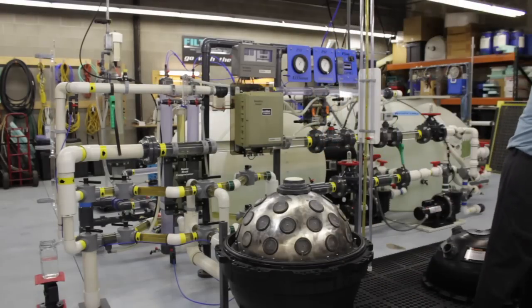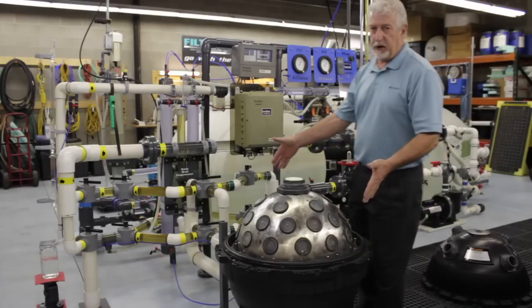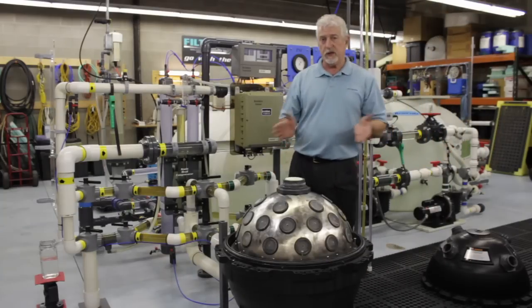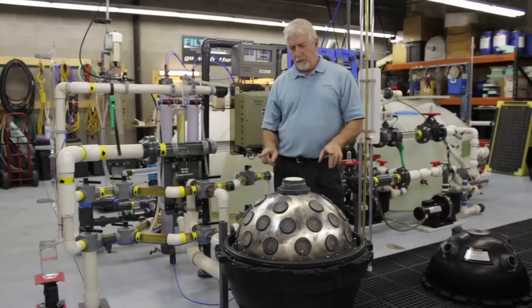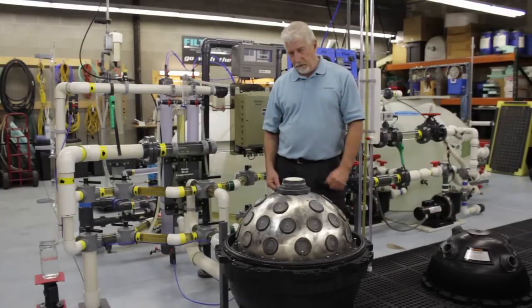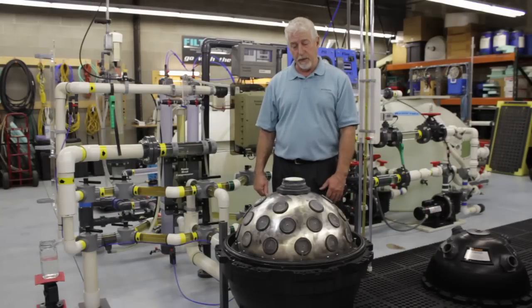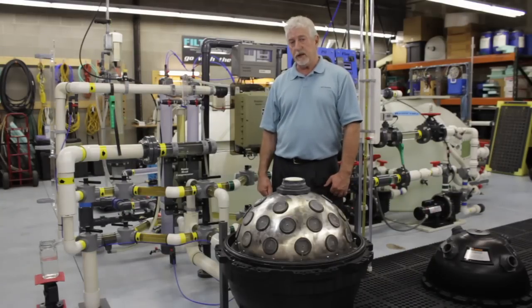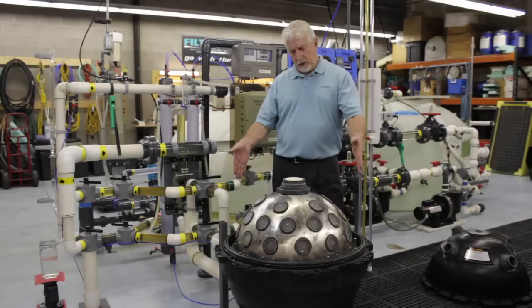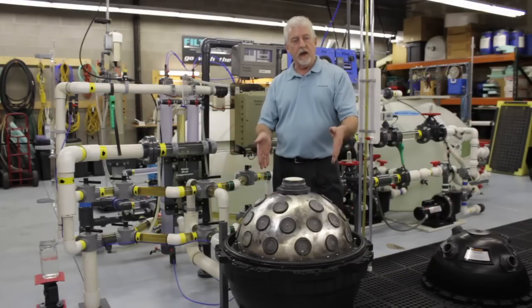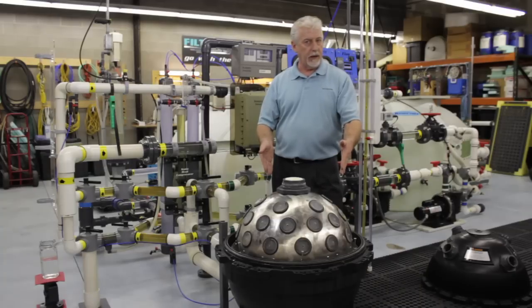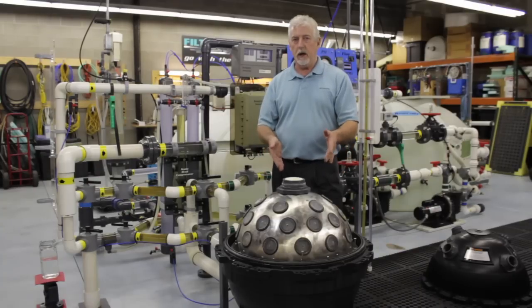This initial prototype was built in a 24-inch filter tank that normally was designed for sand and had a peak flow of 68.5 gallons per minute. As a radial flow, it had 3-inch pipes. It had a peak flow of 210 gallons per minute. The future units we intend to build are smaller. We intend to build a 100 gallon per minute that'll be housed in an 18-inch diameter tank, and a 20 gallon per minute that'll be housed in a 10-inch diameter tank.